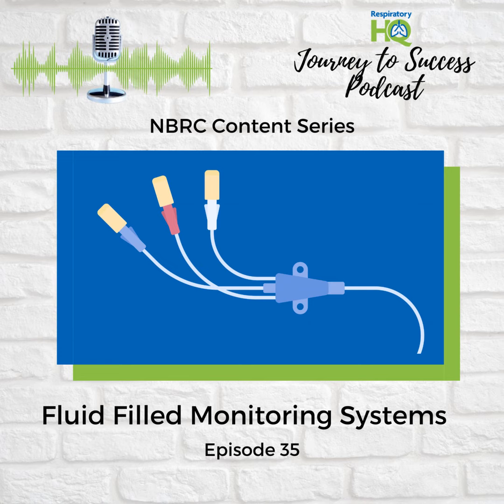Our source mentions this automatic flush device and a pressure bag. What do those do? Those are essential. They keep the whole system working properly, like keeping the pipes clean. The pressure bag has saline solution, sometimes with heparin to prevent clotting. It's constantly pushed through the catheter and tubing. I see. This keeps blood from backing up and clotting in the catheter, so you get accurate readings. It's pretty amazing how much precision goes into all this. I never realized how important it was to prevent air bubbles. Oh, yeah. Tiny things can make a big difference.